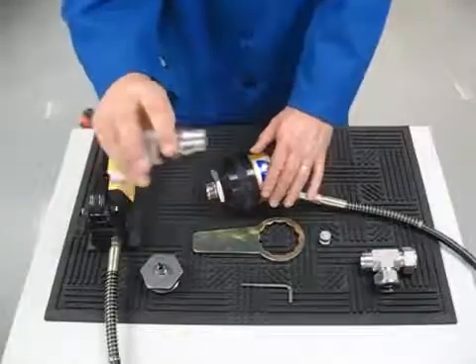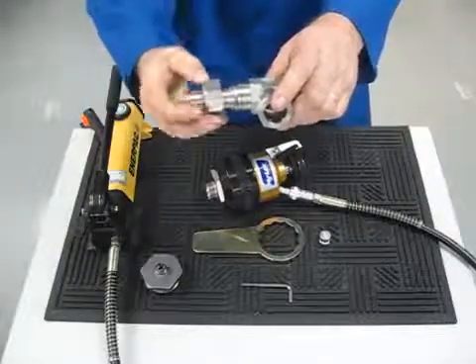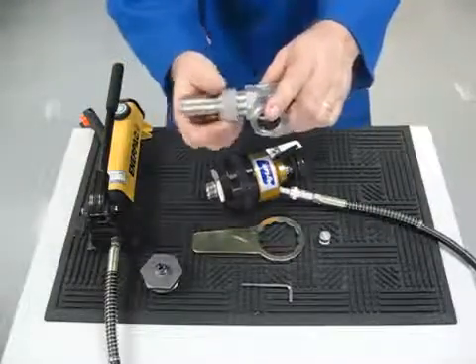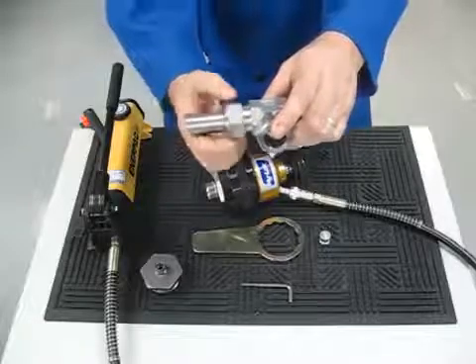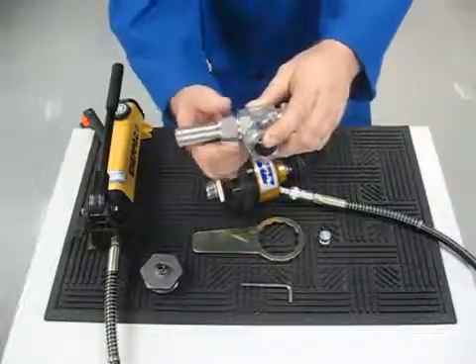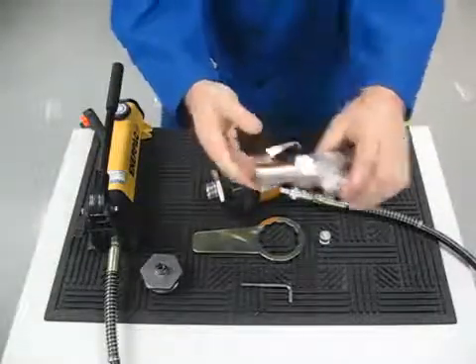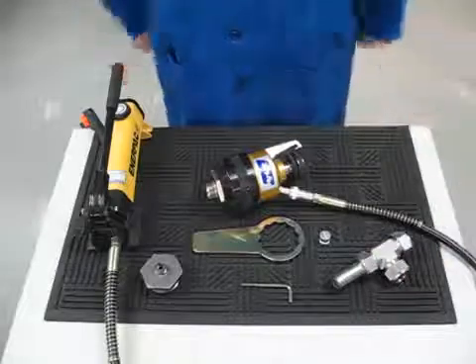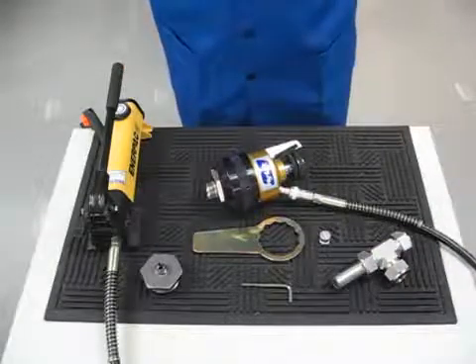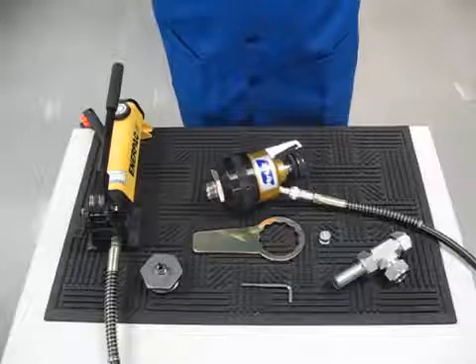To complete the fitting installation, insert the preset ferrule set into the fitting body and tighten the nut hand tight. For the one inch tube fitting demonstrated here, tighten a half turn from hand tight to fully install the Hy-Lok fitting. For sizes under one inch, tighten with a wrench a quarter turn from hand tight.